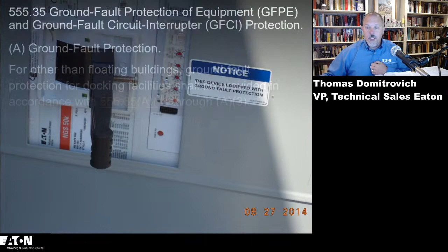Now, what we said in here was, for other than floating buildings, ground fault protection for docking facilities shall be provided in accordance with A1 through A3, and the receptacles providing shore power. So any receptacle providing shore power, and you have to understand what does that mean? So shore power, I'm going to read the definition for you out of the code book. It says the electrical equipment required to power a floating vessel, including but not limited to the receptacle and cords. So we know that when we use the term shore power in 555, it is anything that's powering a vessel.